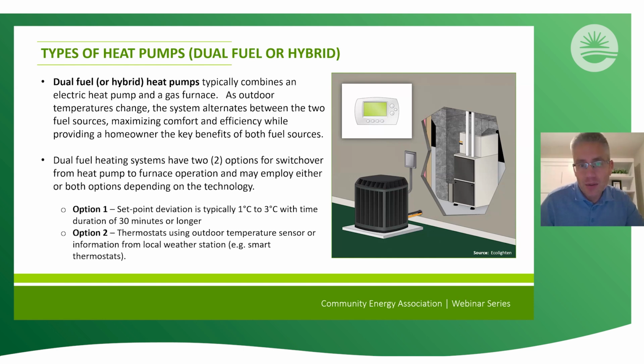And so that might be an outdoor temperature sensor, or it might be information from a Wi-Fi thermostat, or a Wi-Fi thermostat that takes local weather station data. So for example, you may have heard of ecobees and Nests. What they'll do is use the temperature from a local weather station to determine what the outdoor temperature is, and then have a switchover utilizing that.